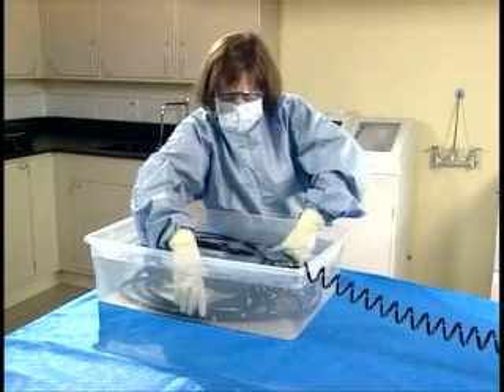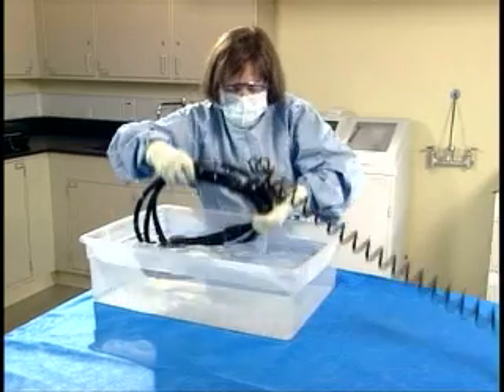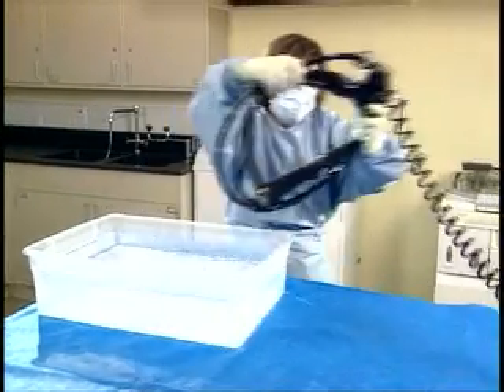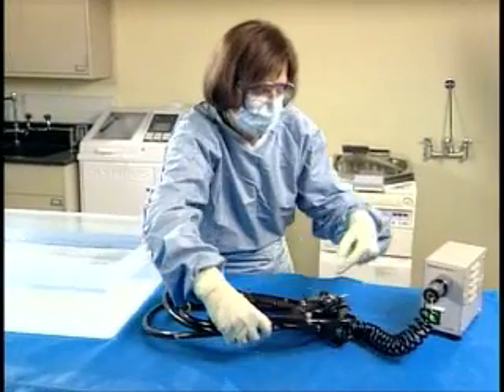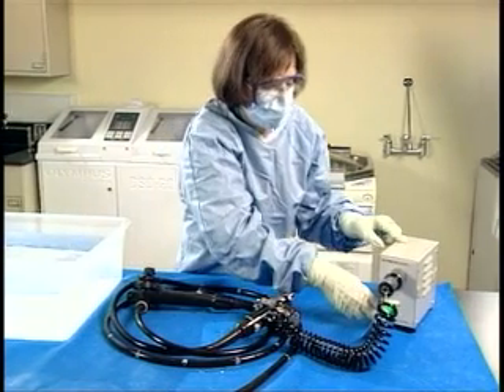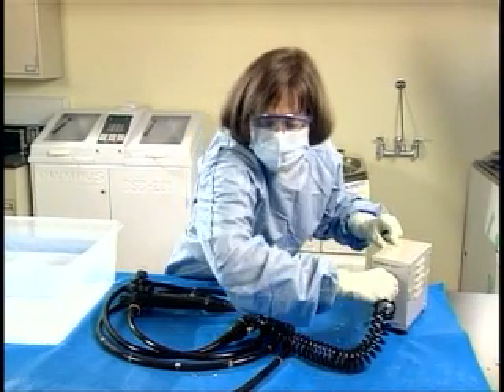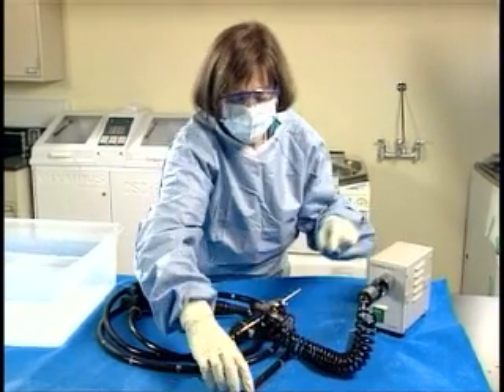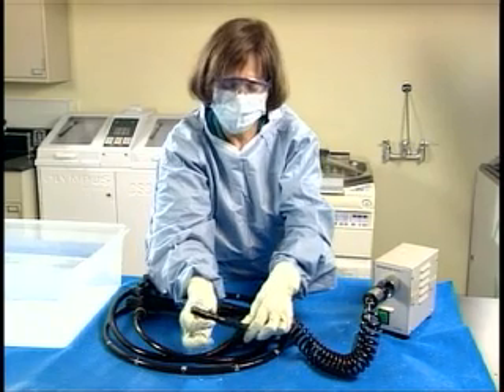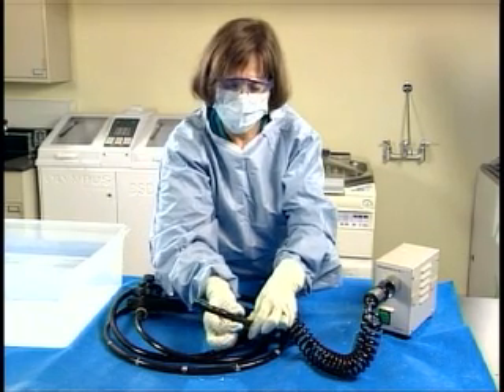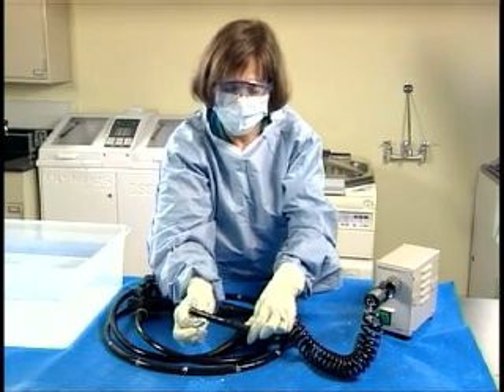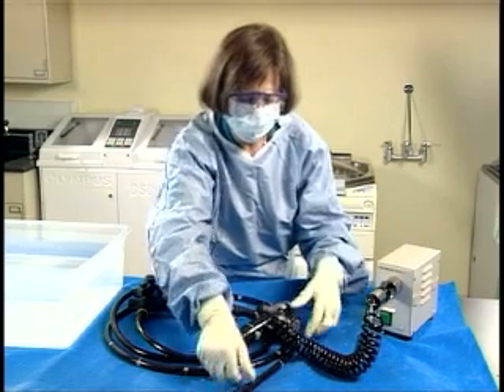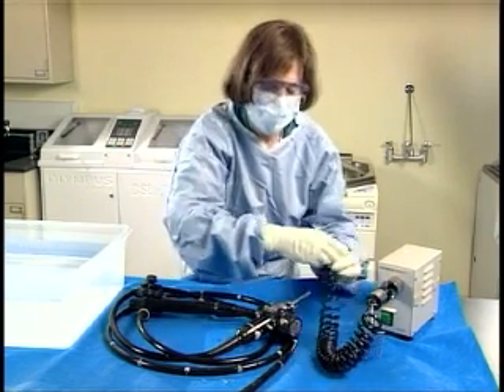If no leaks are observed, remove the endoscope from the water. Disconnect the leakage tester from the air supply and wait for the bending section rubber to return to its normal size. Detach the leakage tester from the water-resistant cap. Leakage testing is now complete.